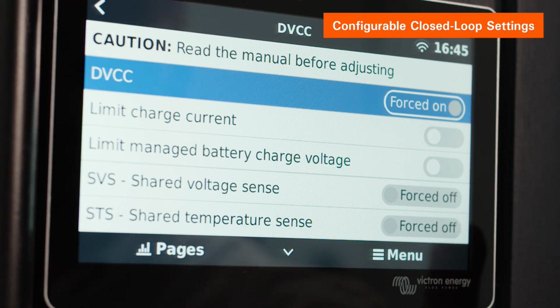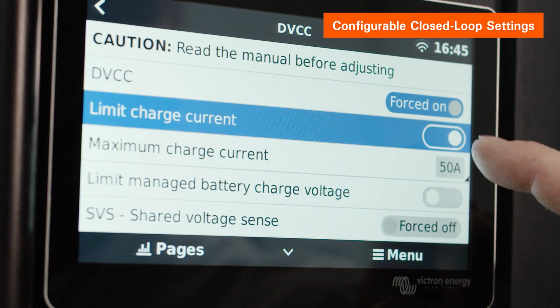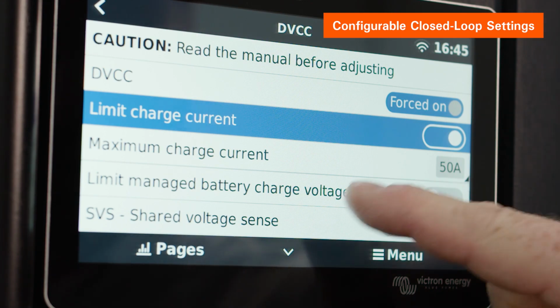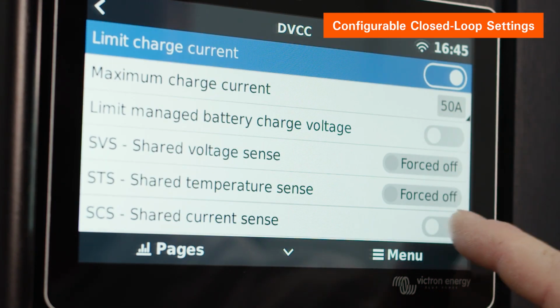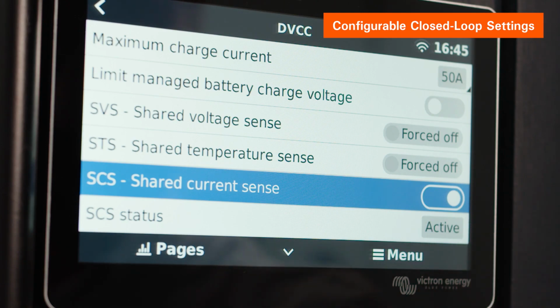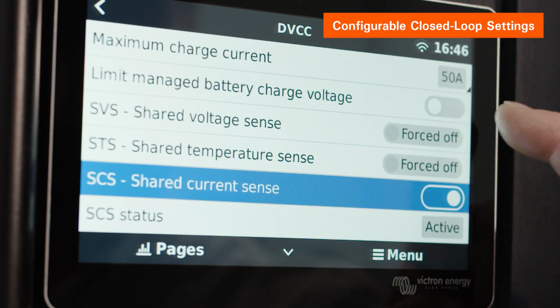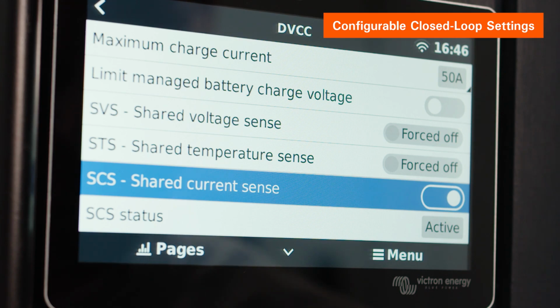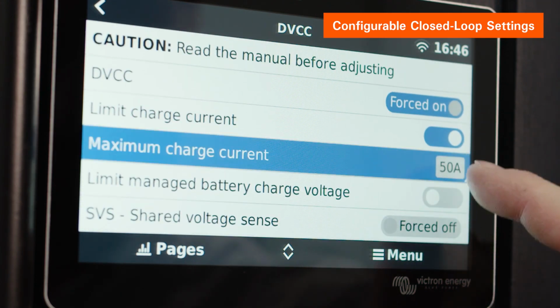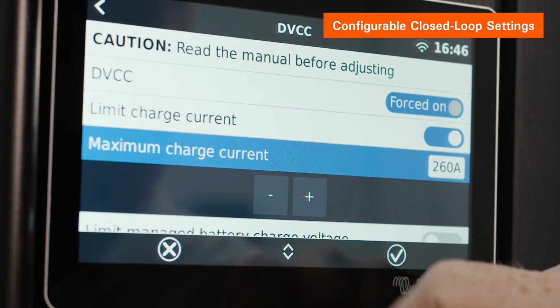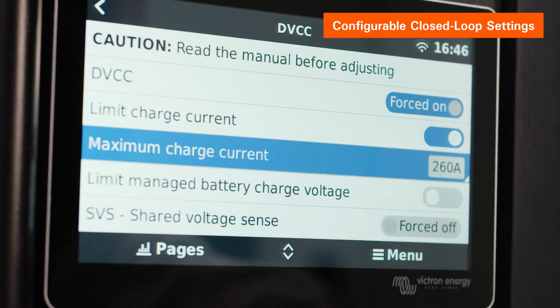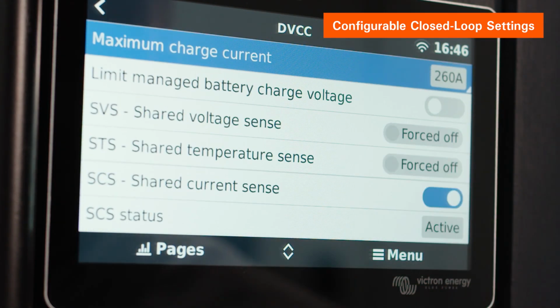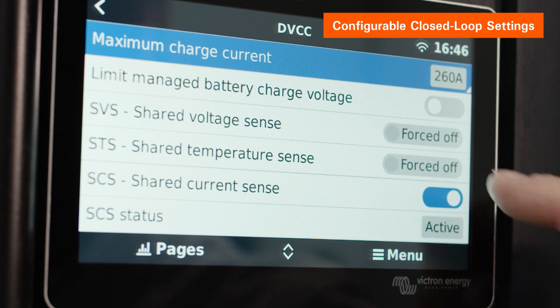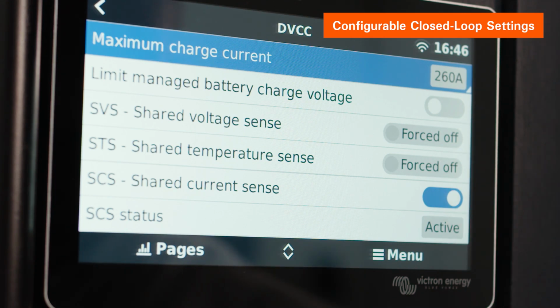Ensure that DVCC is forced on and that limit charging current and SCS are both on. Limit managed battery charge voltage should be disabled. Set the maximum charge current to the installed number of Discover Lithium batteries multiplied by their rated maximum charge current, or a lower value if curtailment is required. SVS and STS should be forced off. After all menu items have been set, reboot the system.